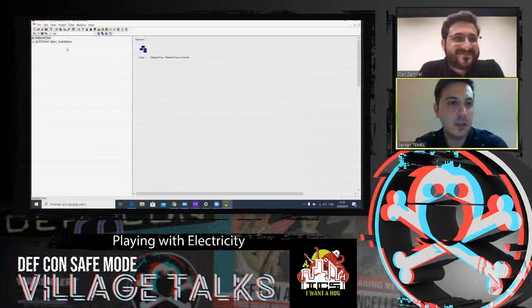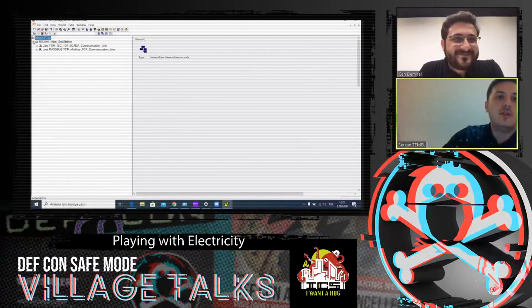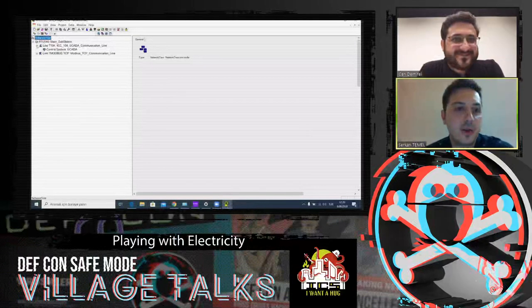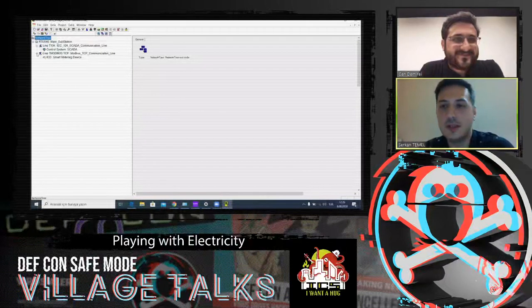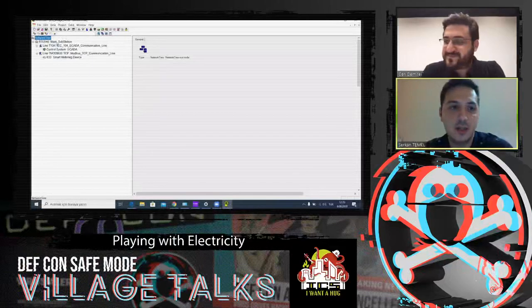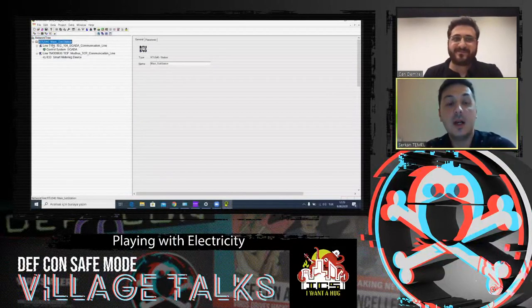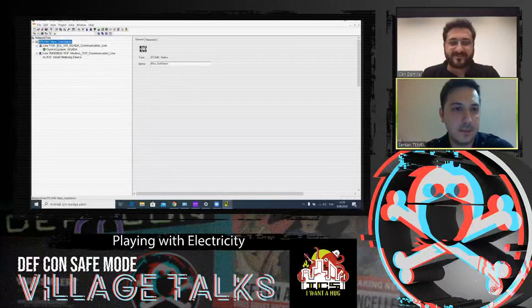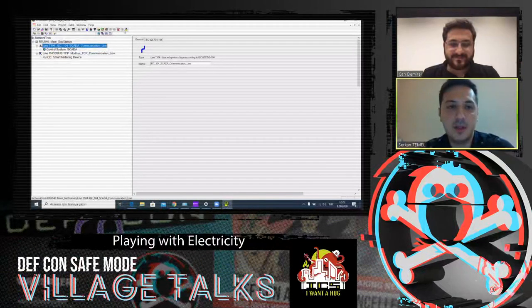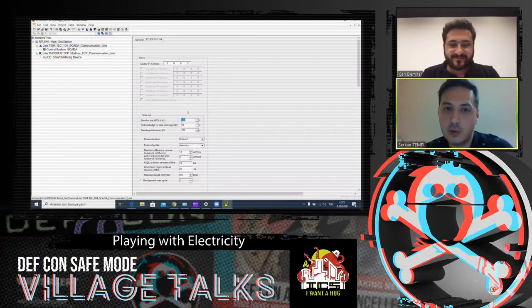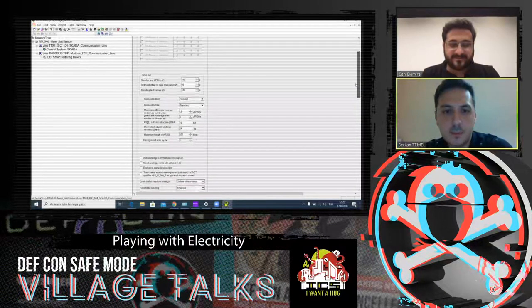Now, this is the RTUtil 500 software interface. This is the network tree. We have three communication lines. One is IEC 104 for SCADA communication. The other one is Modbus TCP for the IED device, the Modbus communication line. You can easily see some parameters of the communication protocol. Yes, this is the 104 communication protocol setup.